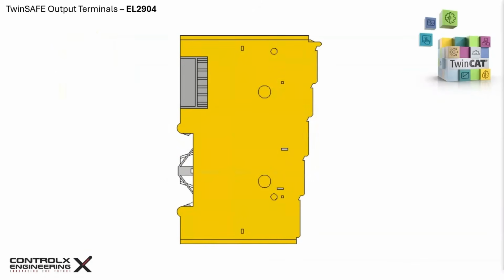On the EL2904, the TwinSAFE address is set using a 10-position DIP switch block on the side of the terminal. This defines the terminal's unique FSoE address, which the logic controller uses to identify the device during safe communication. Each switch position represents a binary value, which allows us to assign a wide range of valid FSoE addresses between 1 and 1023, to ensure every safety device on the network is uniquely and securely identified.